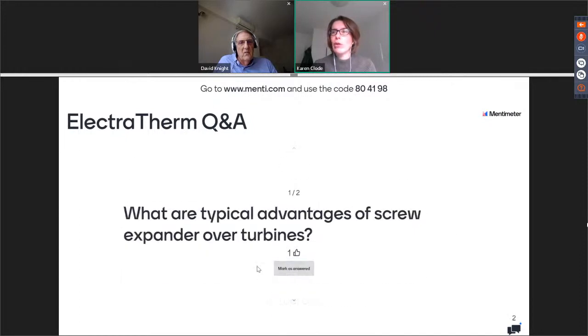What's the typical advantage of screw expanders over turbines? We operate at a slower speed. The twin screw expander runs at 3,500 rev per minute, while a turbine runs much higher. The other huge advantage is if your heat load changes and reduces, so you don't fully evaporate your working fluid, we still operate safely. It will not damage the twin screw turbine. Basically, our power output will go down because there's not as much pressure passing through the twin screws, and then as the heat comes back, we just ramp back up and go. So from a safety point of view, if you've got variable heat load, the twin screw expander is an advantage.